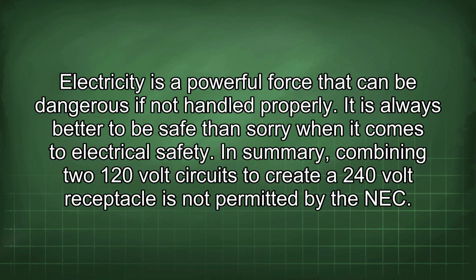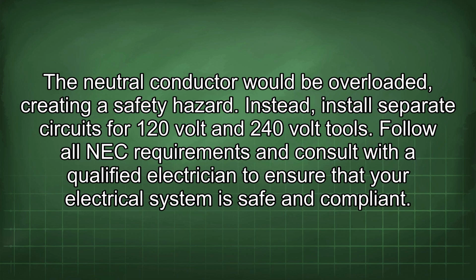Electricity is a powerful force that can be dangerous if not handled properly. It is always better to be safe than sorry when it comes to electrical safety. In summary, combining two 120-volt circuits to create a 240-volt receptacle is not permitted by the NEC. The neutral conductor would be overloaded, creating a safety hazard. Instead, install separate circuits for 120-volt and 240-volt tools. Follow all NEC requirements and consult with a qualified electrician to ensure that your electrical system is safe and compliant.